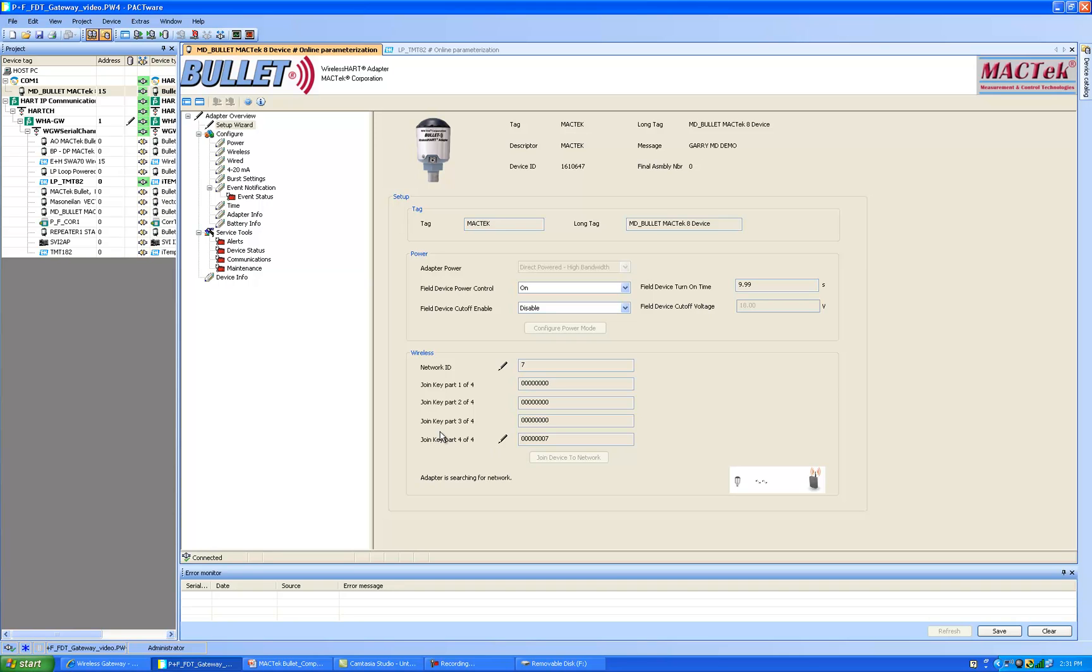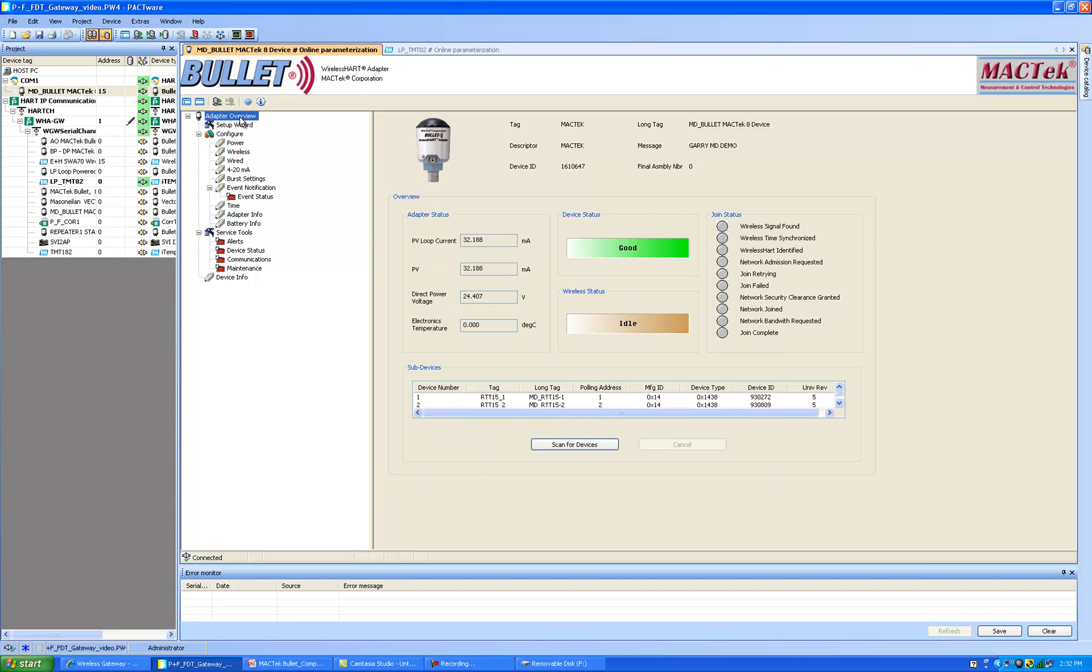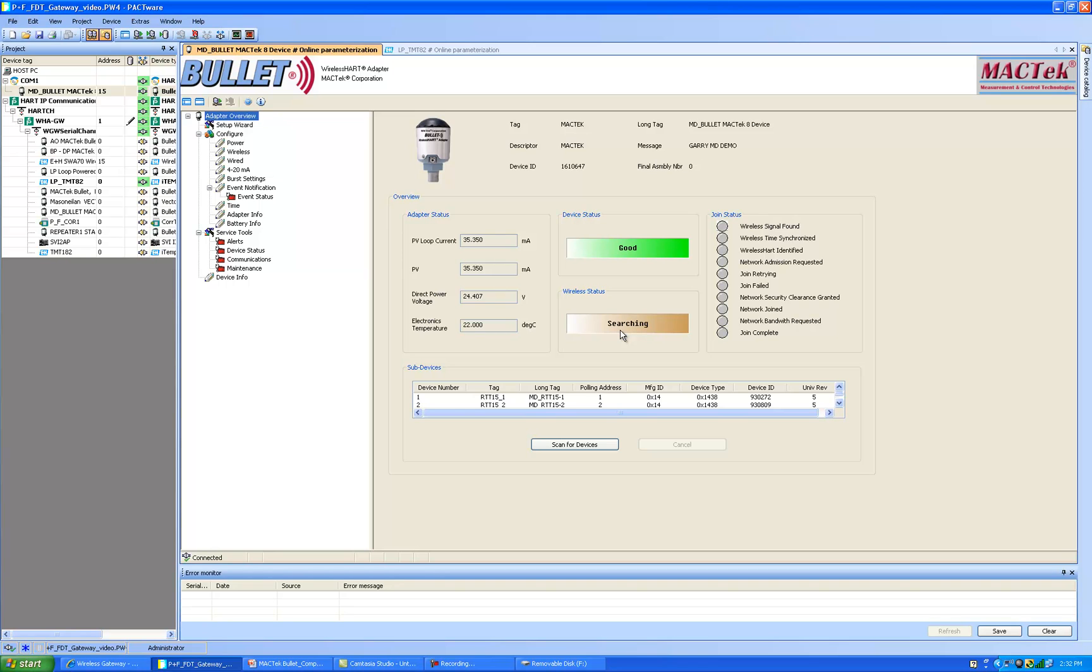The DTM will write this information to the bullet. Now we select the overview page and you will see the bullet is now in idle and it will start to search for the wireless network and as different parameters are met we will see the Christmas tree light up. We just switched to searching. So now the bullet is actively looking for a wireless HART gateway, the one with network ID 7. Now we'll see that the bullet has found the wireless network. It has synchronized times and the wireless HART signal has been identified.